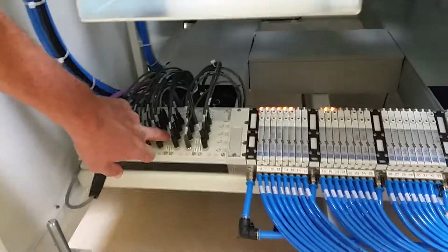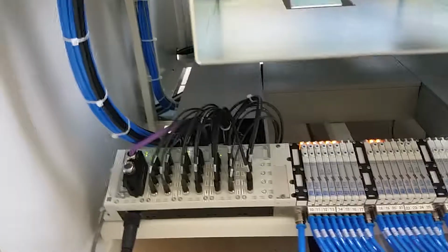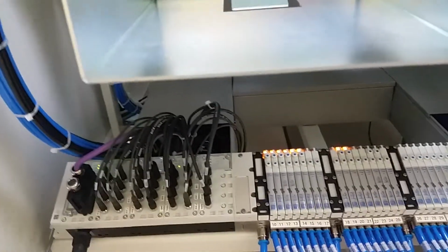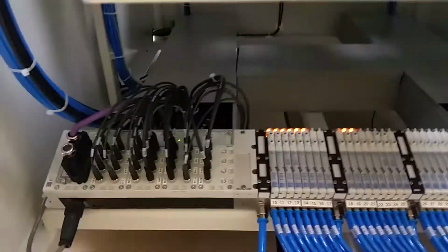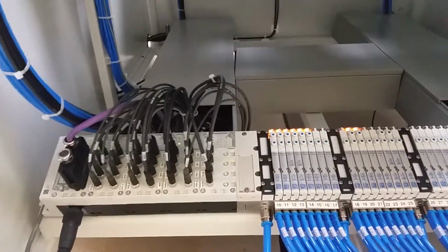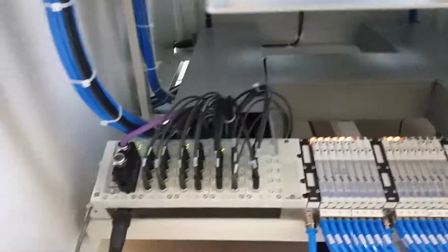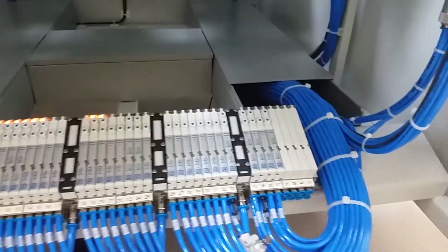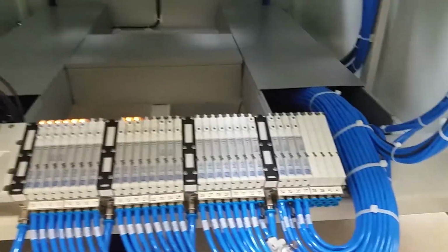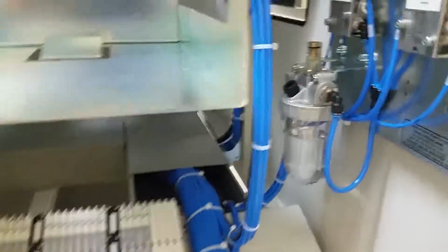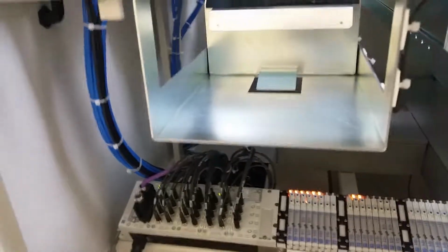Then down here on this bank, you'll look for your SAP sensor connections. And they're all marked. Everything's marked. On the rare occasion you get one where the LED goes off on the sensor but not down here, either your cable or your sensor's bad. So that's all the sensors in this block, and all the pneumatics are over here. And you've got sensors for your cylinders, telling it certain positions, that are tied in down there.